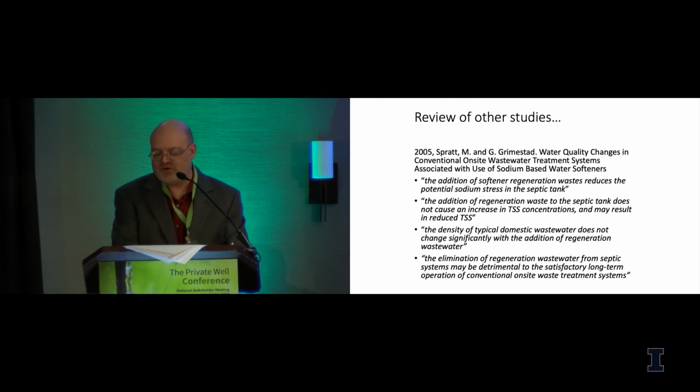And the addition of regeneration waste to the septic tank does not cause an increase in TSS concentration and may result in reduced TSS. And the density of typical domestic wastewater does not change significantly with the addition of regeneration wastewater. And finally, the elimination of regeneration wastewater from septic systems may be detrimental to the satisfactory long-term operation of conventional on-site waste treatment systems. So again, another study that indicated there may be some detrimental impacts of diverting the softener discharge.